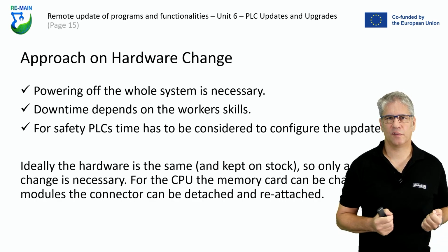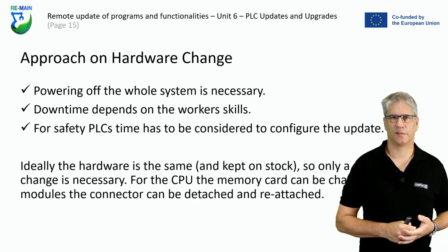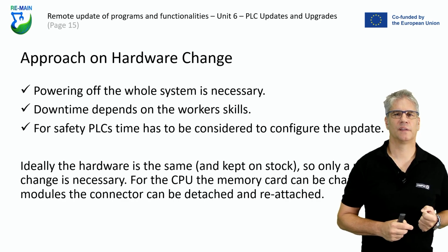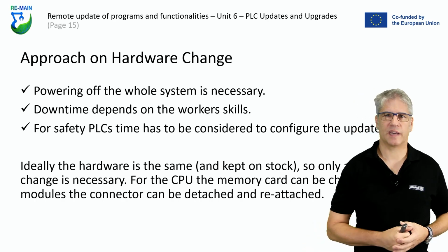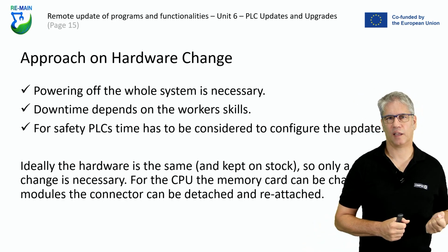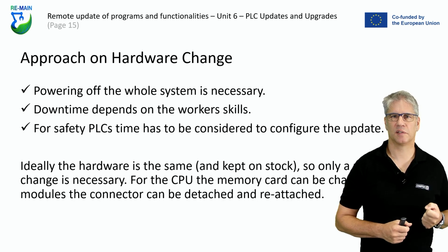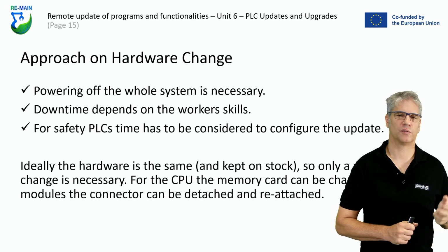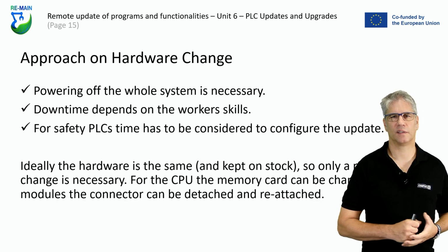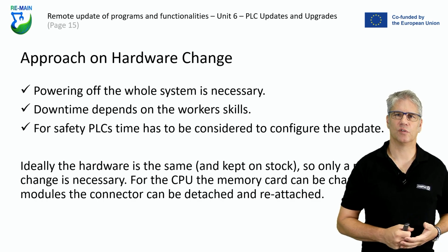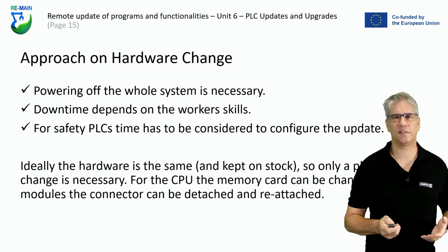Nevertheless, the downtime then will depend on the worker skill. So if the parts are available, then you can change them. So ideally, the hardware is already on stock. In automotive industry, you are obliged to use only a few types of PLCs exactly for that reason. They are kept in stock, and if there is some hardware failure, they just replace the PLC or the I/O modules. You take out the memory card, change the CPU, and insert the old memory card in the new CPU and continue working. So the downtime will be minimized, and this is essential.